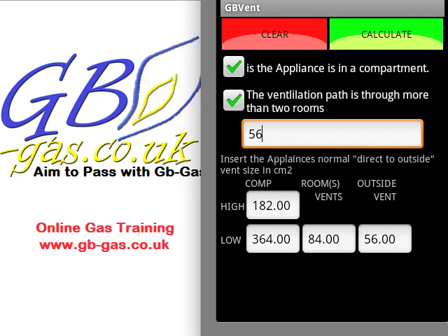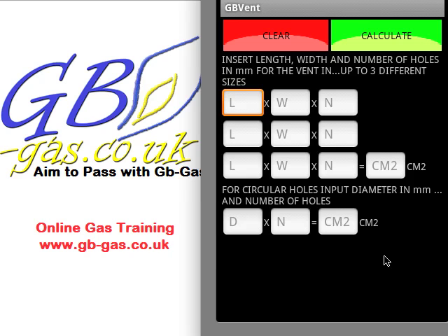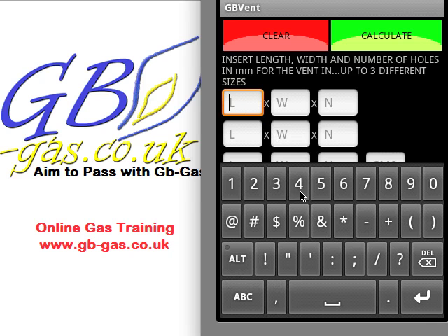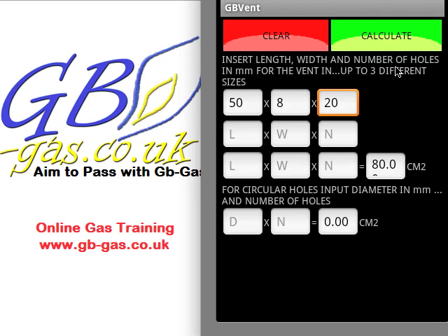Let's hit the back button again and look at the vent size checker. If we're calculating the size of a ventilator that's already installed, we need to know the length, the width, and the number of holes in that vent. The top section has space for three different sizes. We keep the length in millimetres — it could be 50 mm long, the minimum width is between 5 and 10 mm for a gas vent, let's make it 8 mm, and let's say there are 20 holes. When we hit calculate, it tells me that ventilator is equivalent to 80 cm².